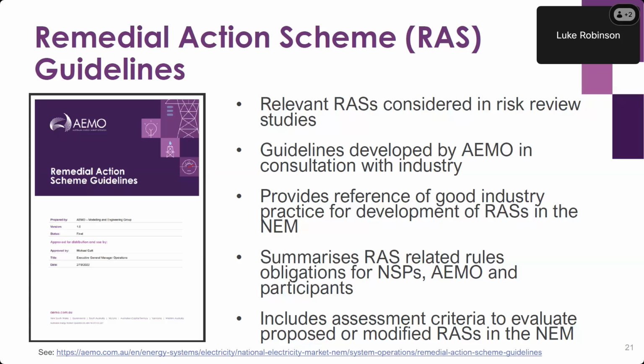And because there's a wide range and increasing number of remedial action schemes across the NEM, as the power system transitions, there's increasing potential for failure to operate or unintended operation of the remedial action schemes that could lead to adverse system impacts such as cascading events and supply disruptions. In the context of the transforming power system and changing operational conditions, it's important that such schemes are reviewed to ensure they remain effective and continue to meet their design and performance requirements. So these guidelines have been designed to address these issues, and I've also provided a link to those on the slide there too.